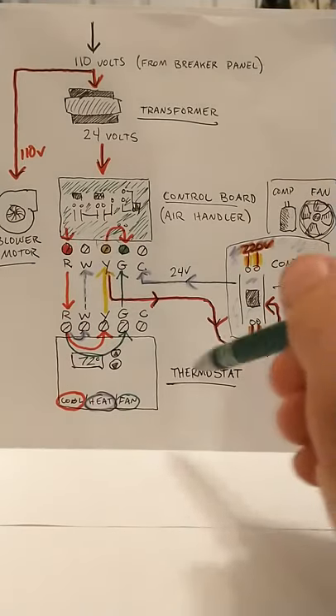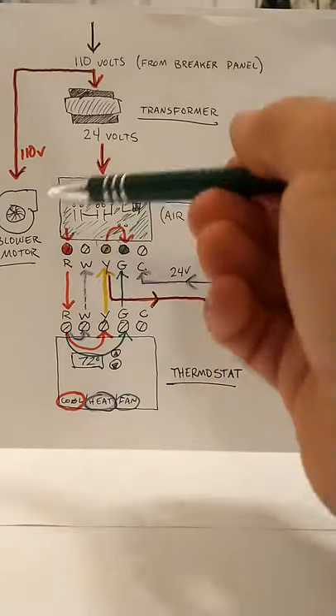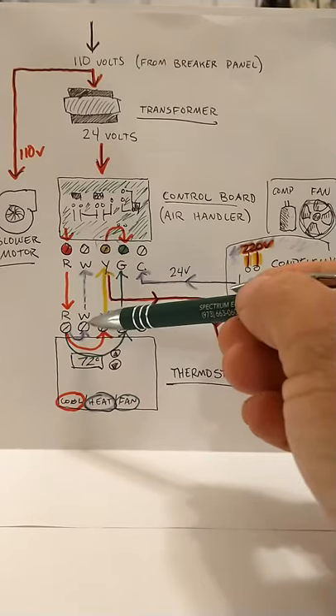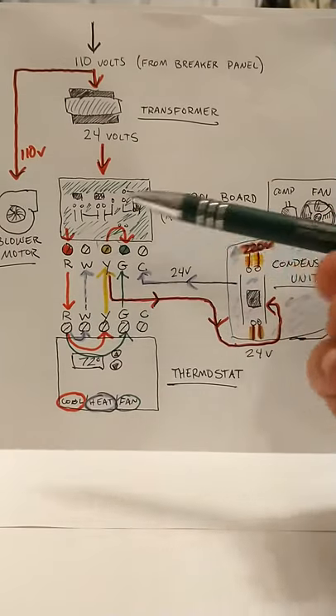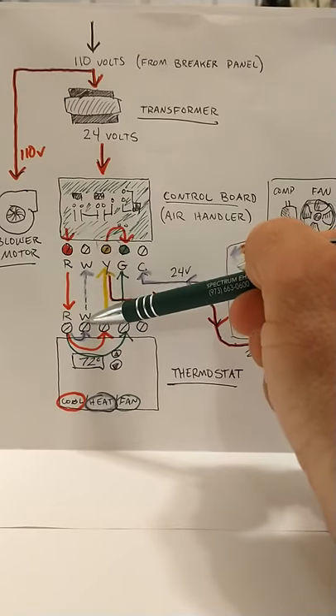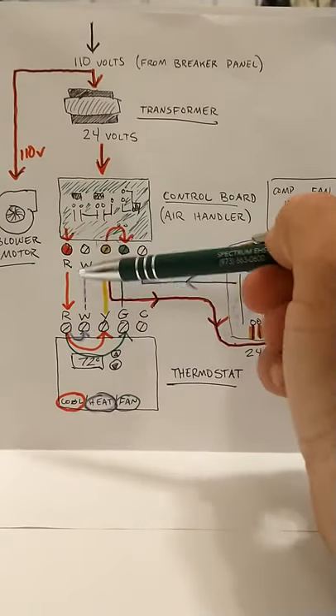Your heating system, when your thermostat's turned to heating, again it'll close the circuit between your R terminal in your thermostat and your W terminal, which is for heating. Your 24 volts will travel from that W terminal to your W terminal at the air handler.